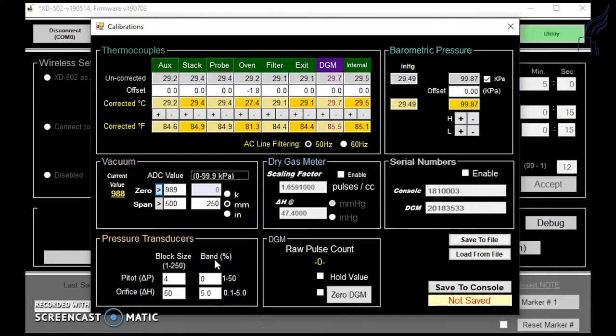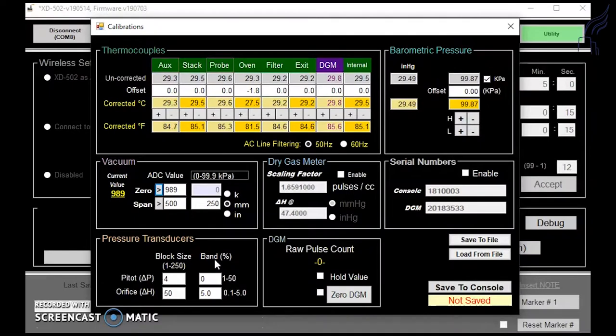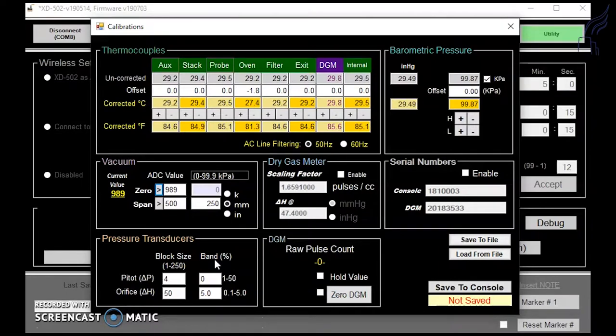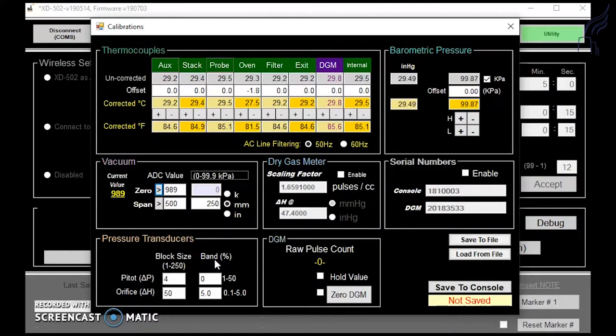If the band percent is disabled by inputting the value is zero, it will never fall out of band and start a new averaging block. Band percent is the percent of transducer full scale. So for example, a band setting of 10% band of the 10 inch pressure transducer is one inch.